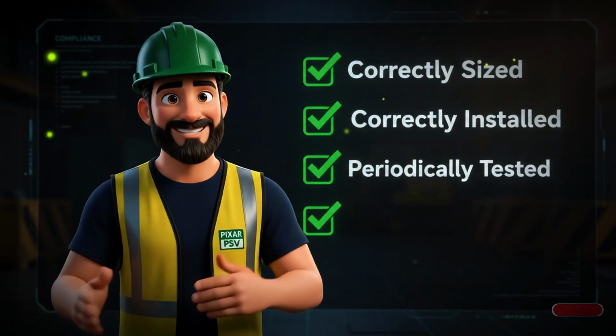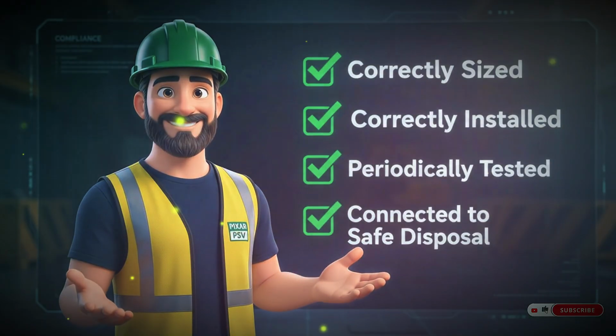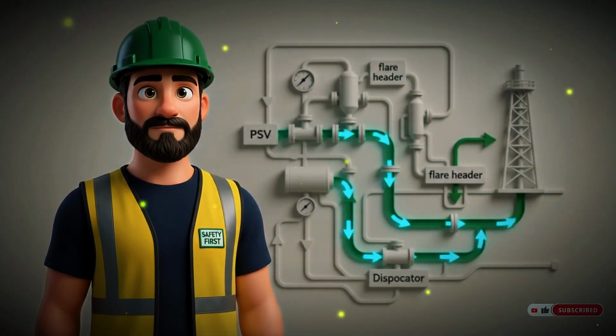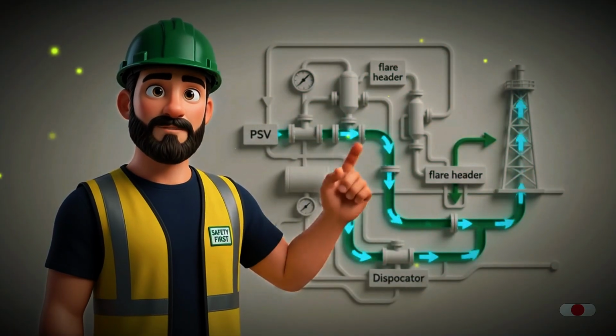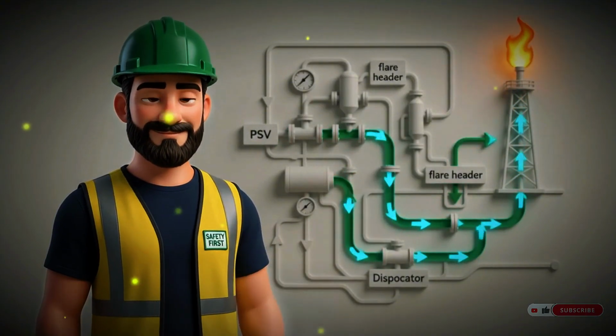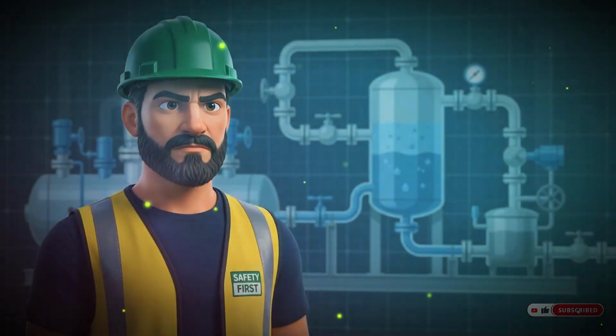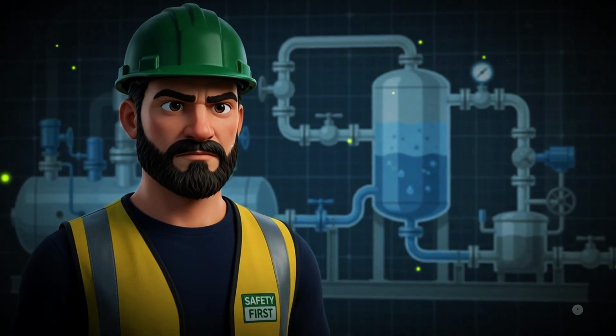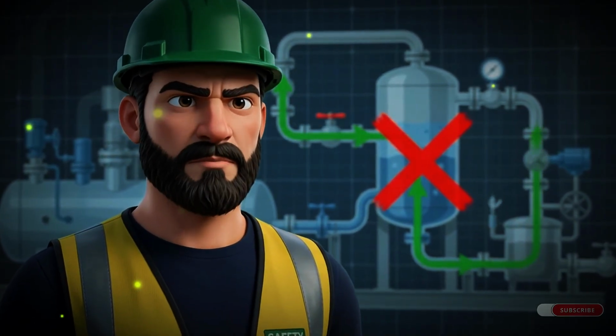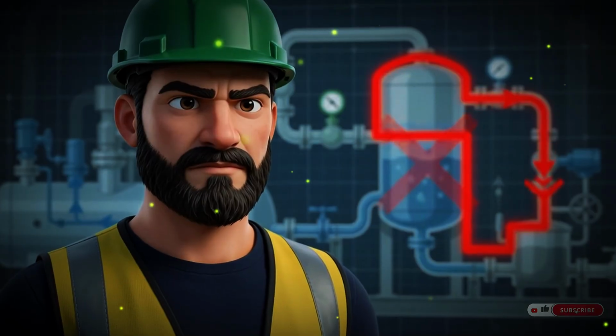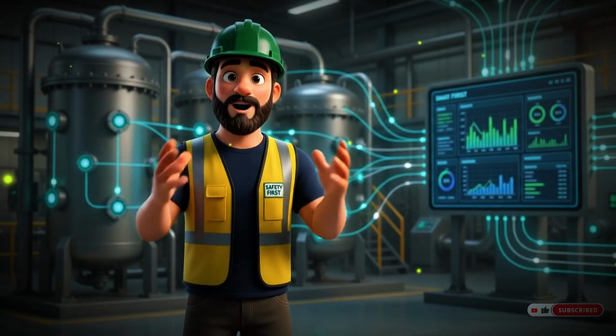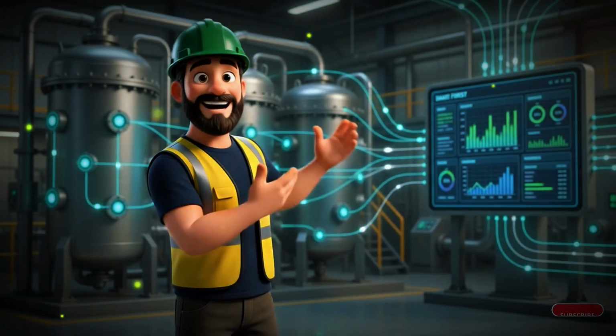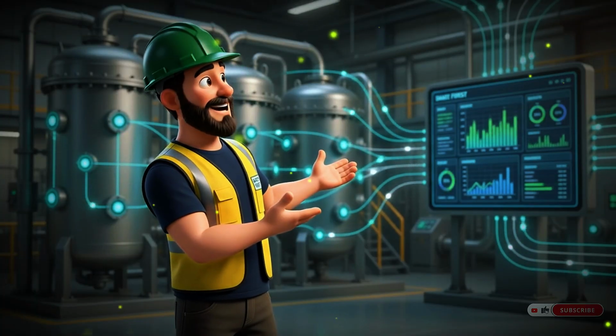It must be correctly sized for the worst-case overpressure scenario, correctly installed, periodically tested, and connected to a safe disposal system for the released fluids, typically a flare system, not a simple vent to the open atmosphere. That is exactly the point where BP failed in Texas City. Today, the technologies available for monitoring and protecting pressure vessels have advanced dramatically from what existed in 2005.